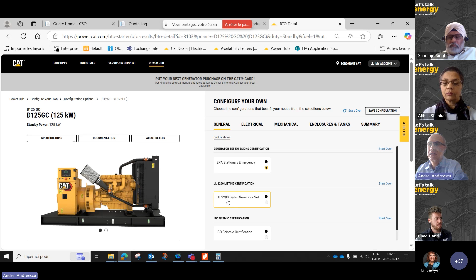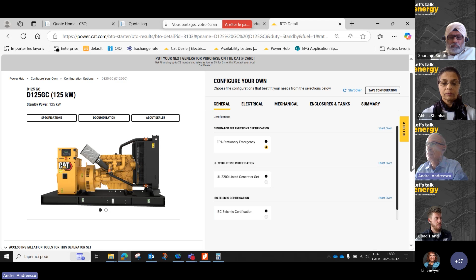The generators are EPA certified. This is a requirement according to the Canadian emission regulations. We may select the UL 2200 generator set if the project were in the United States, which is more applicable for them. We may select the IBC certification for the generator set if, say, we plan to install it in a civil protection building where it is required. For the benefit of the exercise, let's suppose we need this IBC certification.